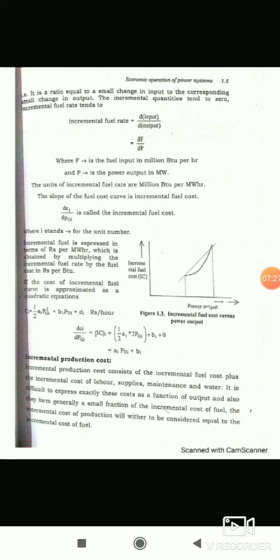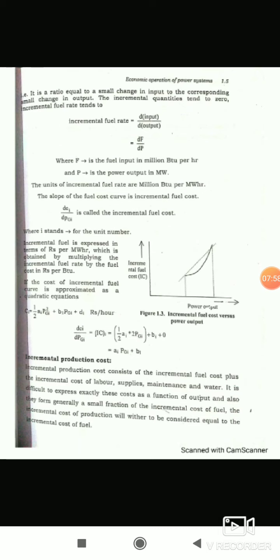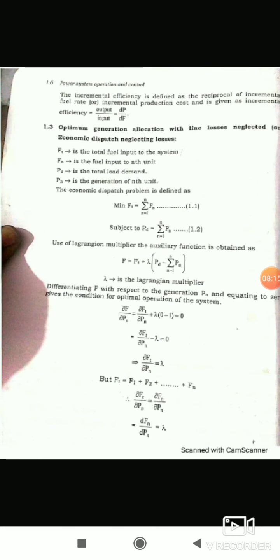Next, incremental production cost. Incremental production cost consists of the incremental fuel cost plus the incremental cost of labor, supplies, maintenance and water. It is difficult to express this cost exactly as a function of output, and it generally forms a small fraction of the incremental cost of the fuel. So the incremental cost of production can be considered equal to the incremental fuel cost. Next, incremental efficiency. Efficiency is output power by input power, and the incremental efficiency is the reciprocal of the incremental fuel rate or incremental production cost. Incremental efficiency is equal to output by input, that is dP by dF.